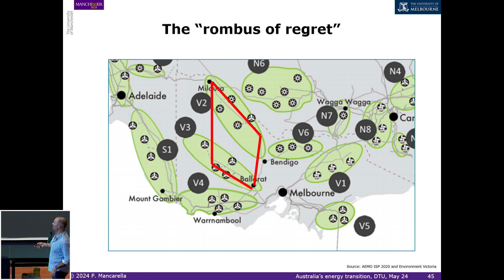So eventually the solution was, instead of running synchronous machines for active power, let's keep running synchronous machines but not providing active power. And of course, what I'm talking about is a synchronous condenser. So I'm still running a synchronous machine, but only to provide the reactive power, inertia, and short circuit current.